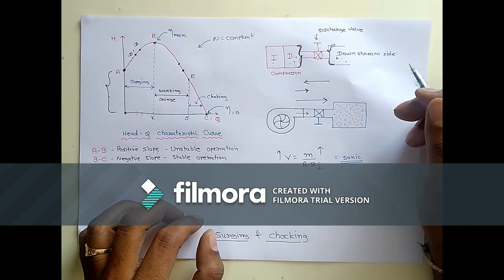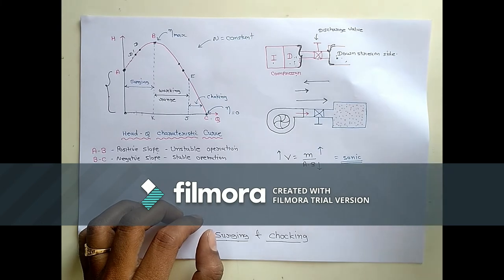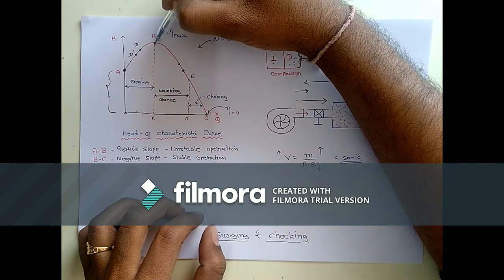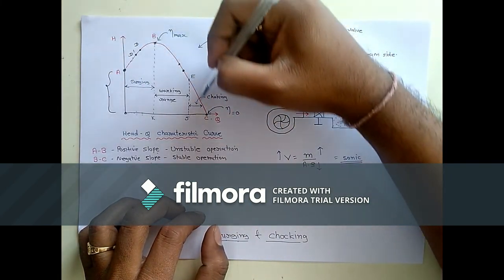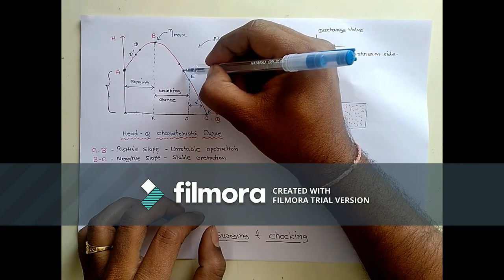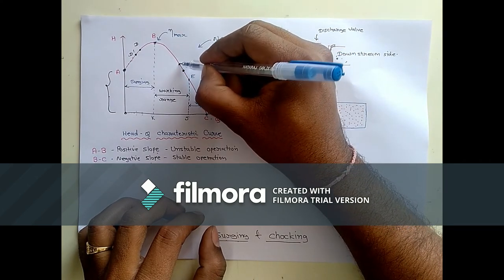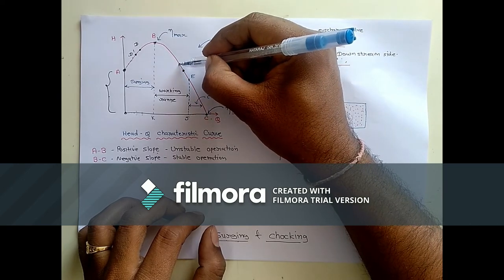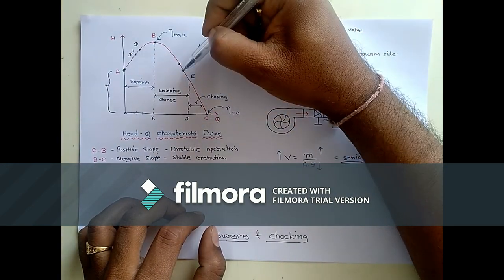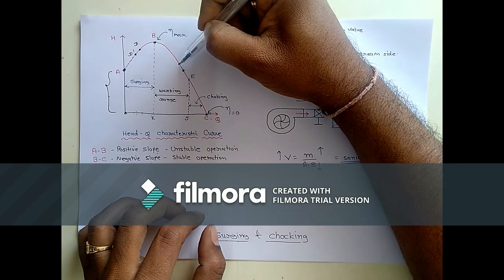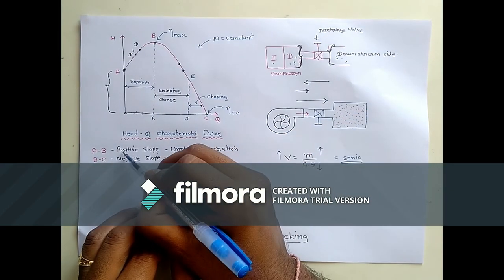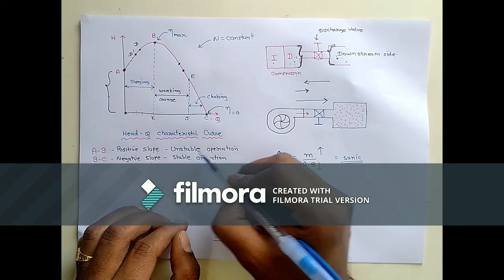The surging problem causes vibration of the compressor parts and is generally avoided. A surge control valve is also used for this purpose. Now, why does surging not occur during the B to C region? As the discharge decreases in this region, the pressure does not decrease — the head increases. So there will never be a reverse flow in this region. Even after decreasing discharge, the head increases from B to C. Surge only occurs on the positive slope side, which is why it is known as the unstable operation region.